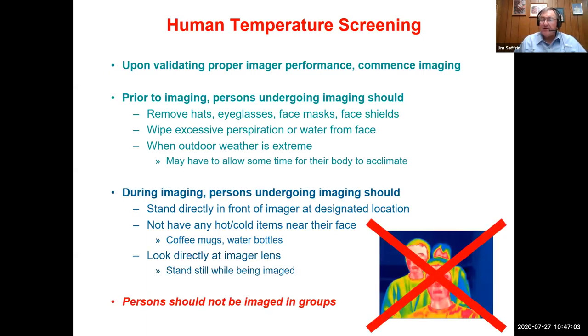Despite what you've seen on TV and the internet, with imaging systems imaging dozens of people or groups of people at a time, this is not permitted under the standards. It's bad technique, and it can lead to oversight of persons who are potentially febrile. So persons should not be imaged in groups, whether or not the imager manufacturer says their imager is capable.